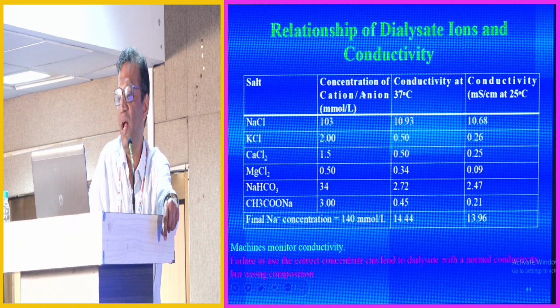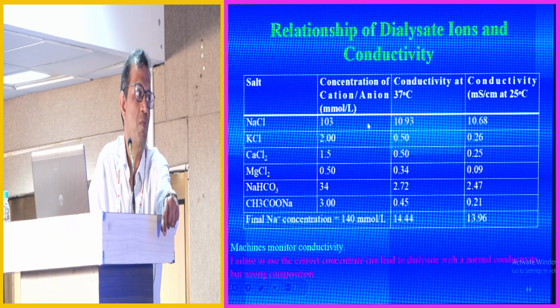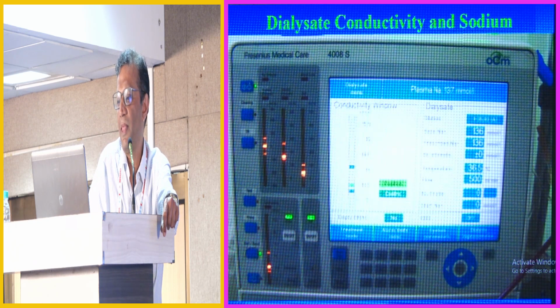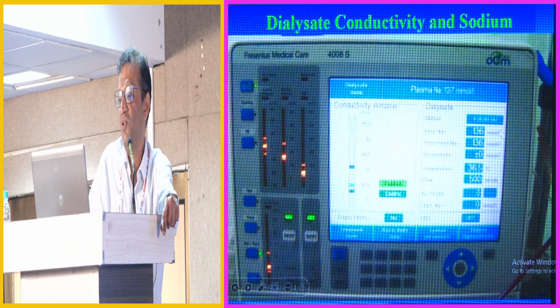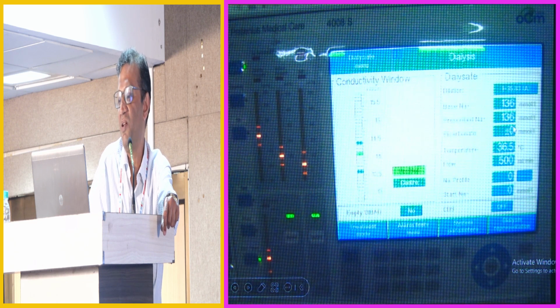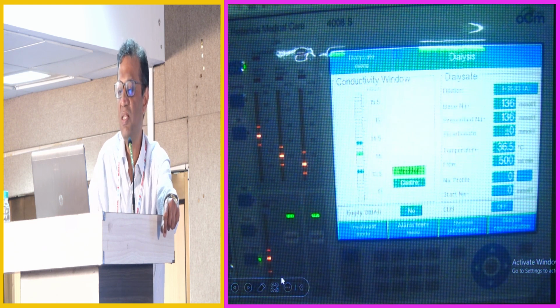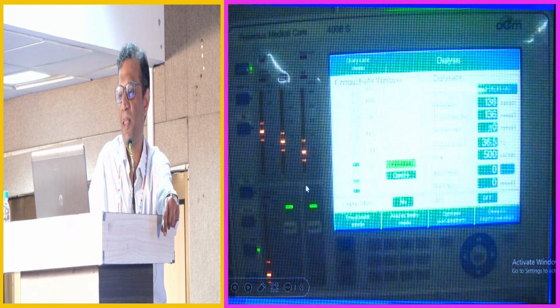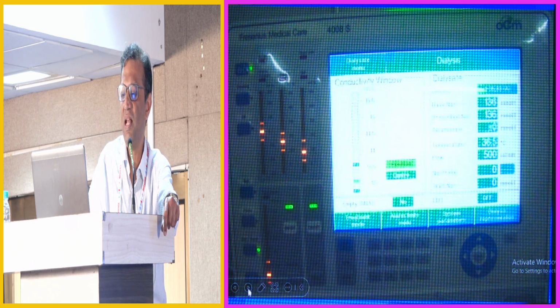The sodium chloride in the dialysate is about 103 millimoles totally and contributes about 10.6 to the total conductivity which we set, and the sodium bicarbonate contributes about 2.5 to the conductivity. Now this looks fine. We've prescribed a sodium of 136 and the machine is saying the conductivity is 13.6. But here it's not. We've prescribed 136 and the machine is saying the conductivity is 14.2. We've prescribed 136 and the machine is giving us a conductivity of 13.2.